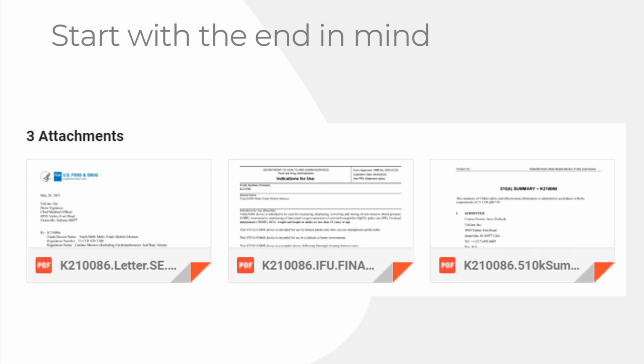The trade-off you're making is that you're agreeing that if somebody requests a copy of your 510K, you will give them a redacted copy within 30 days, and you have to do the redaction, not the FDA. So if that's something you want to do, then you can do a 510K statement. It saves us some time. A lot of our clients say, no, I don't want to have to provide a redacted copy, and they go for the 510K summary.